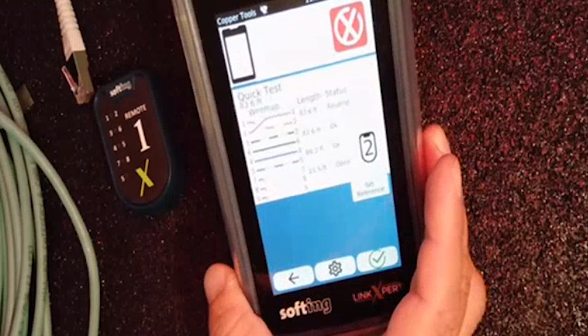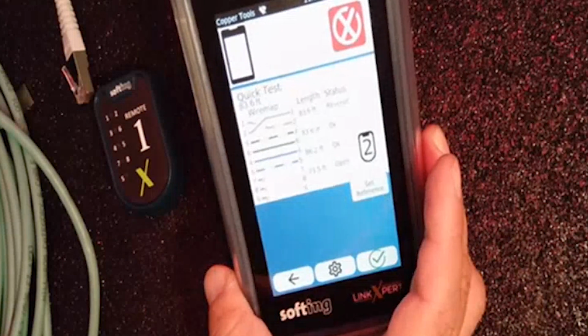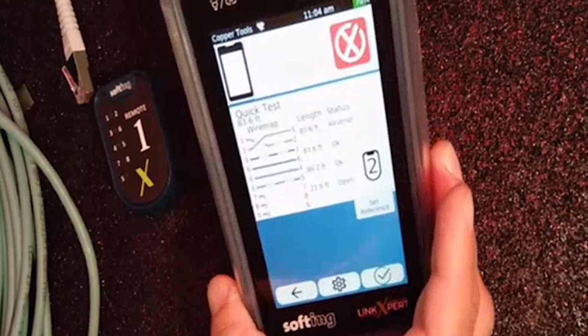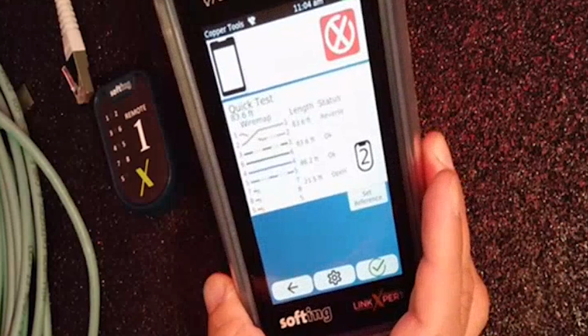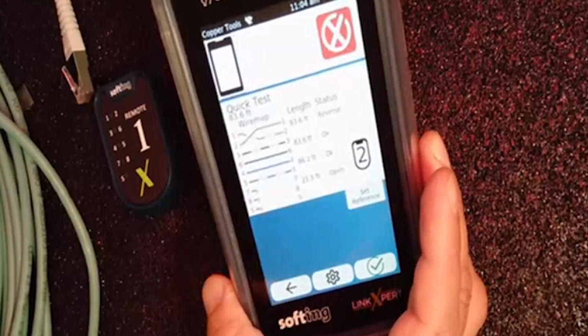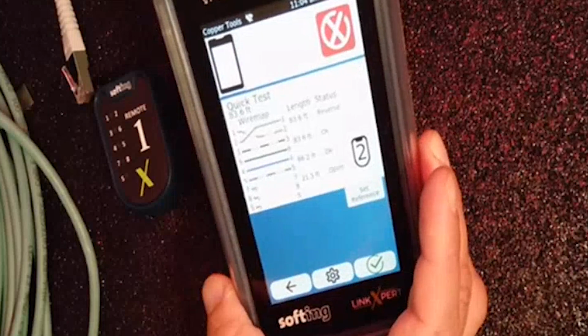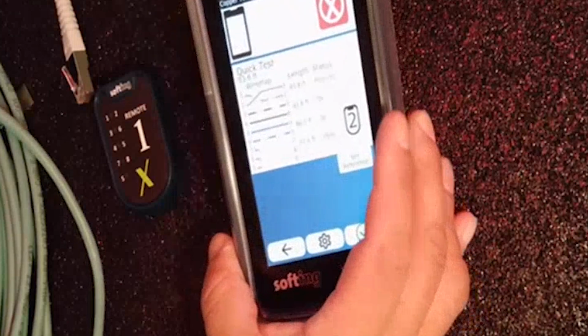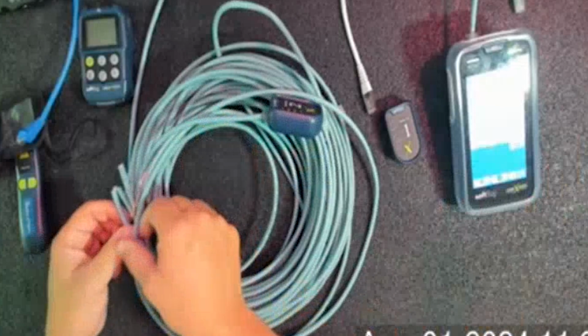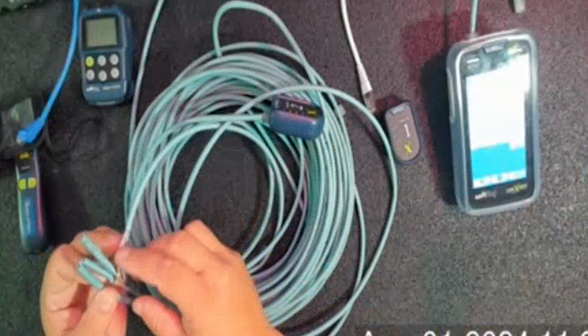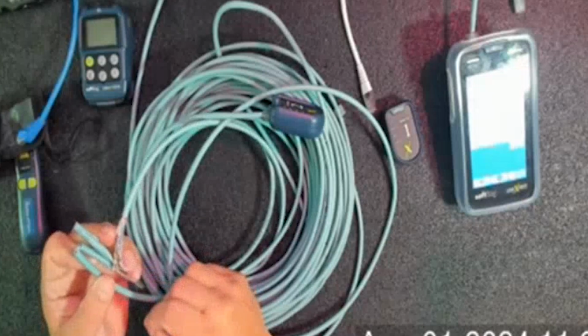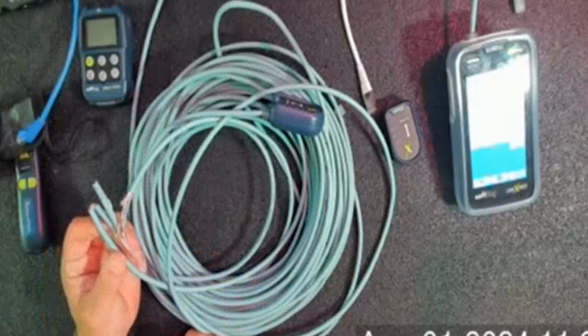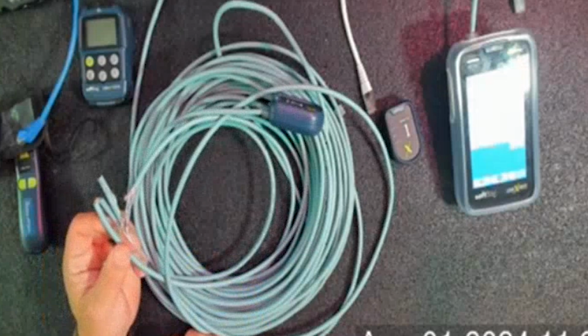What's interesting is it's telling me that open is 21.5 feet long, as opposed to the other pairs which are 80-something feet long. Why is that? Well, if you look into this cable bundle right here in the middle, I do have that open, and if you were to take out a tape measure and check, that would be about 21 feet into that spool.